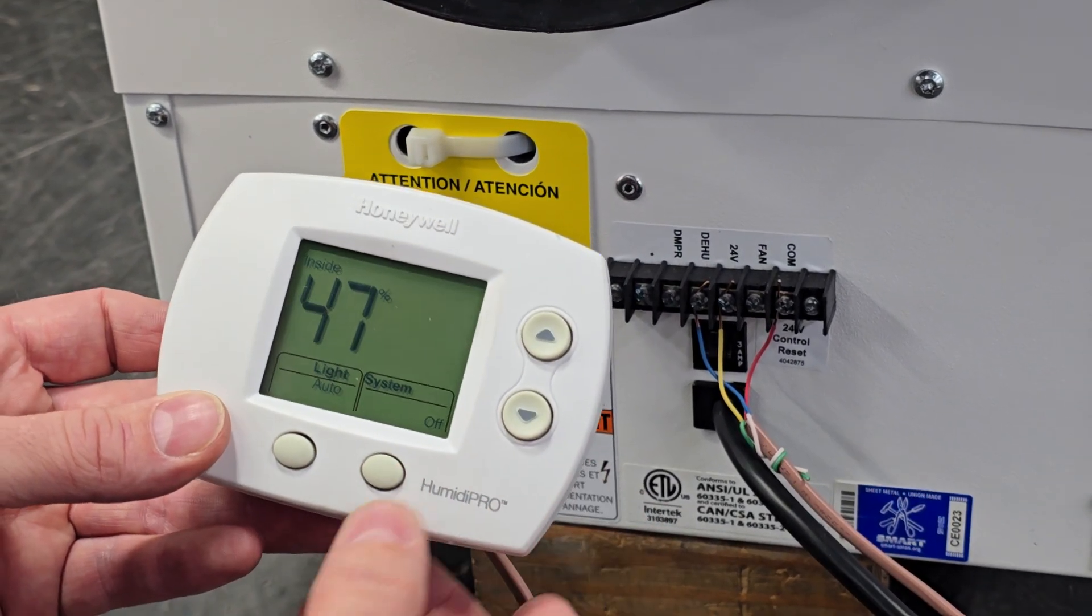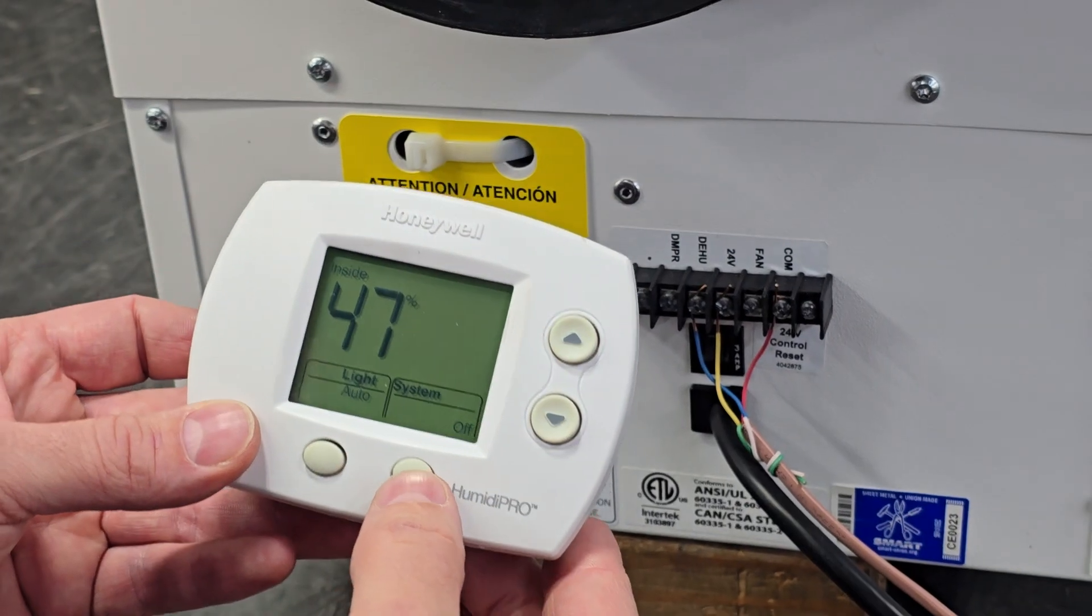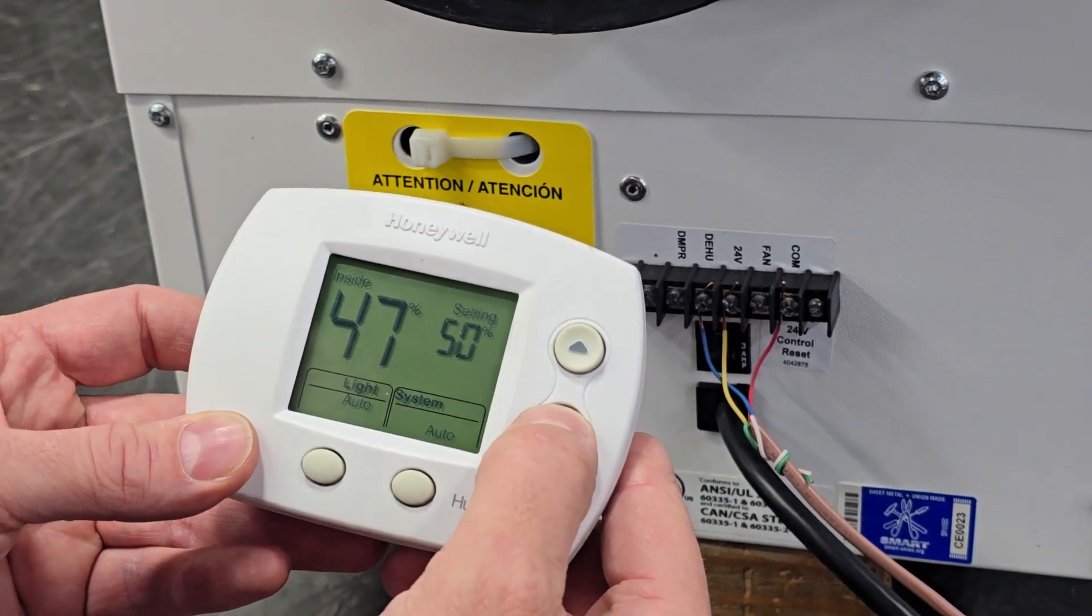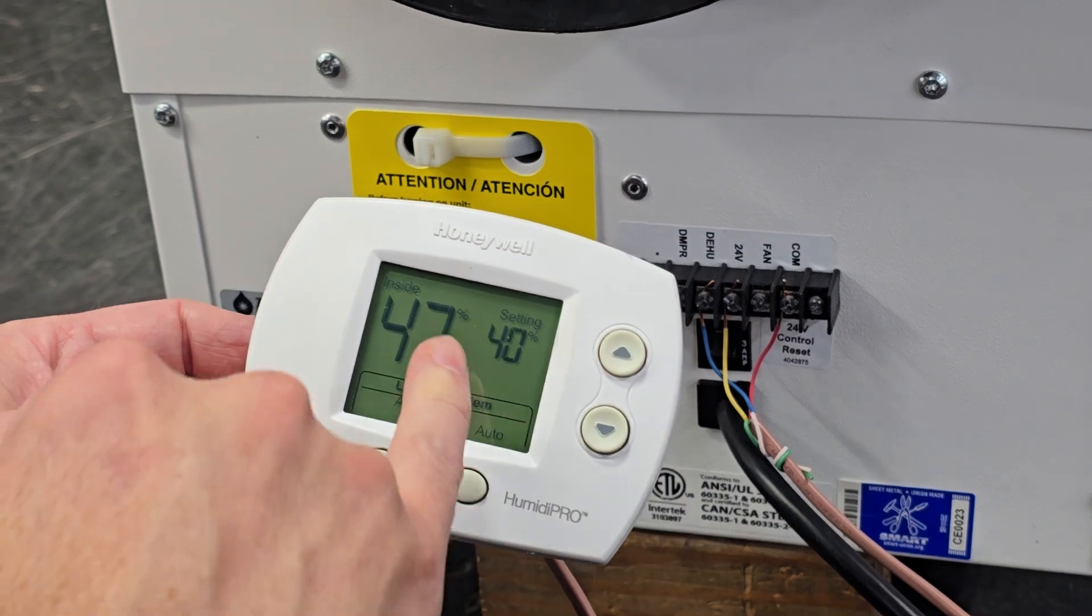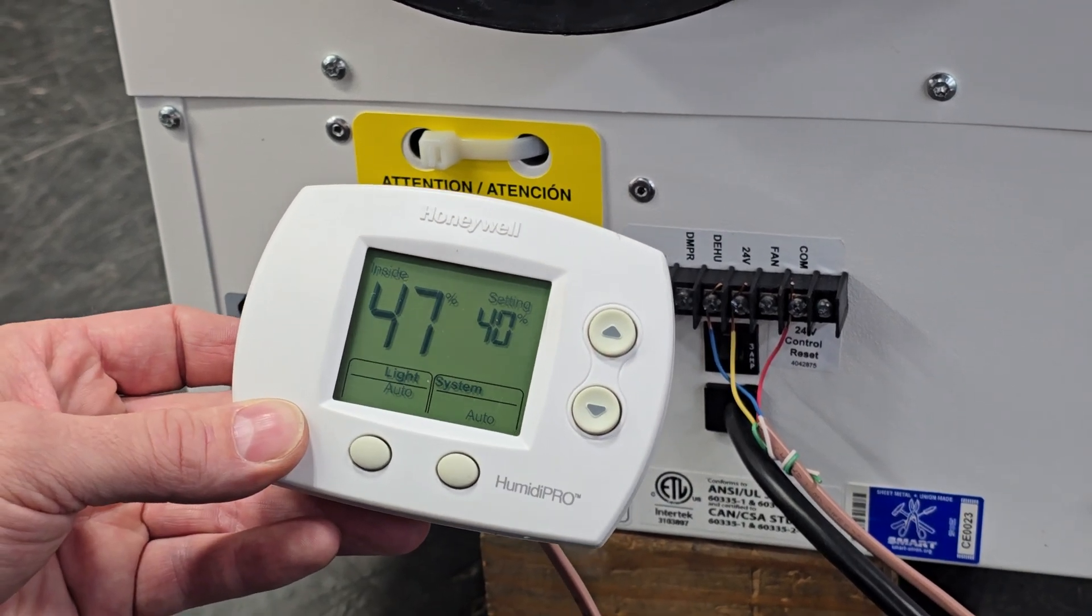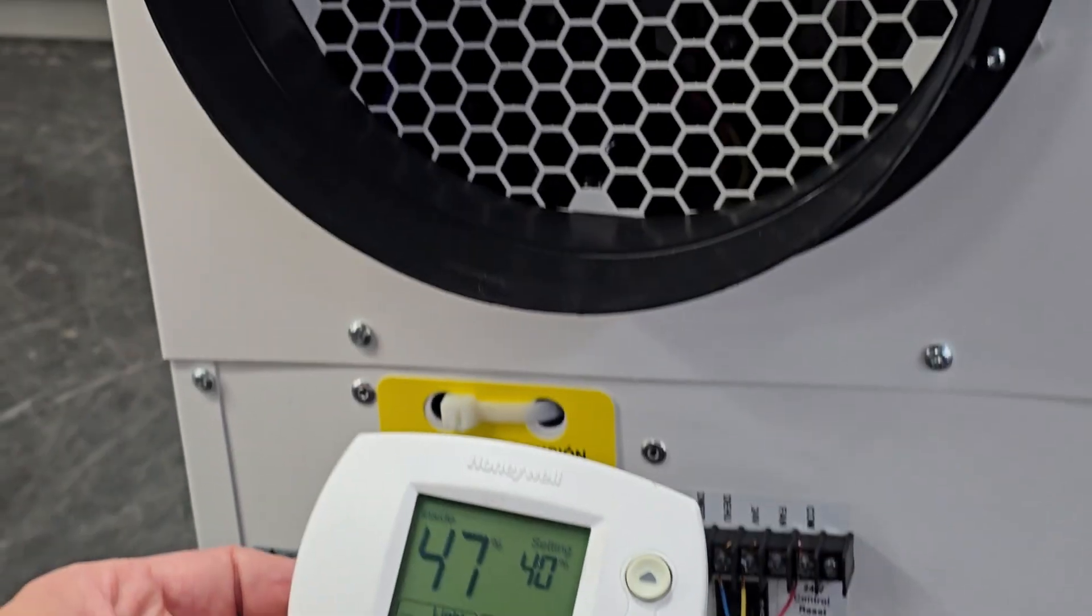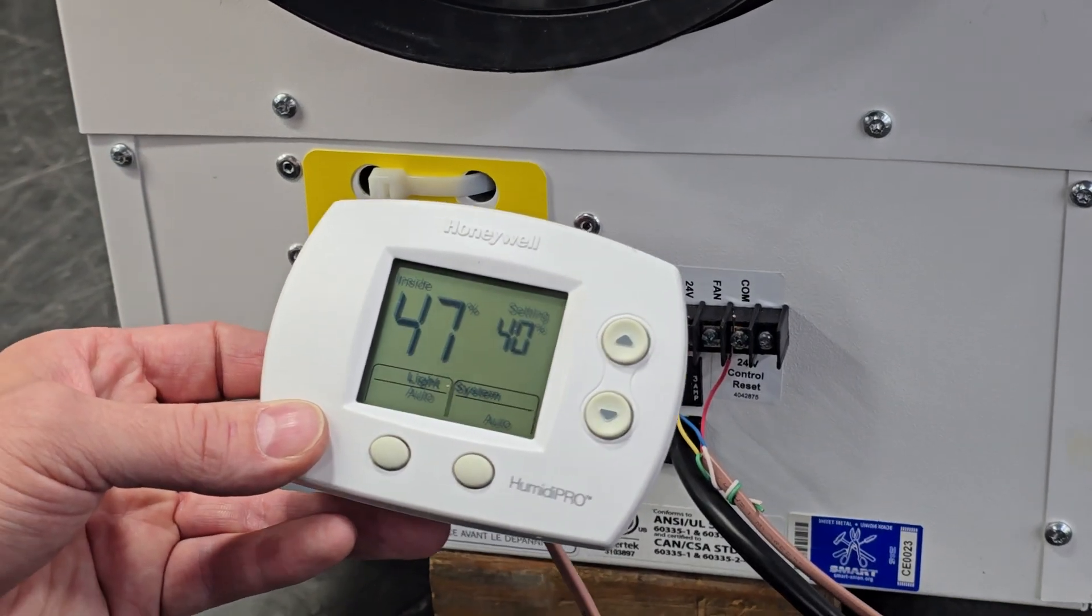And then to check the system to make sure it works, we'll just turn it to auto and then lower the setting below the set point. And then we'll wait for the dehumidifier to come on. We verified the dehumidifier came on, the wiring is complete.